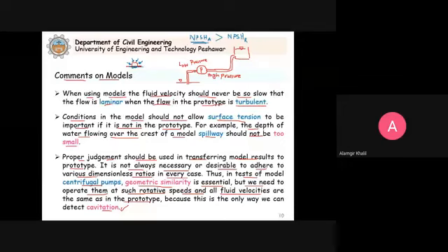That is known as pitting. If we have the metal surface, it will eat the material because of this high impact. And this is known as pitting. Clear? And you see, if it continues, on the surface these small cavities will be created and the material is removed. That's why it is known as cavitation.